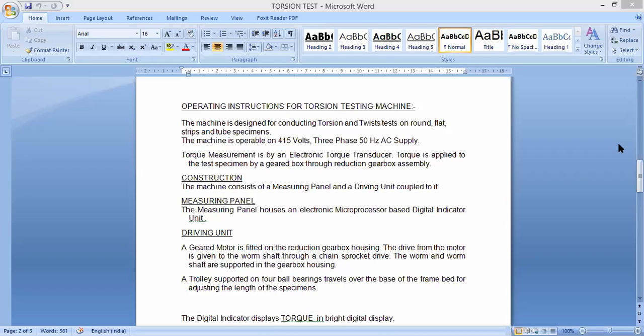The measuring panel, as I've told you, is an electronic microprocessor based digital indicator unit. Its sensor is fixed inside the left face, which senses the twist of the specimen, records the amount converted into torque, and shows it in this digital indicator unit itself. A driving unit, a geared motor, is fitted on the reduction gearbox housing.